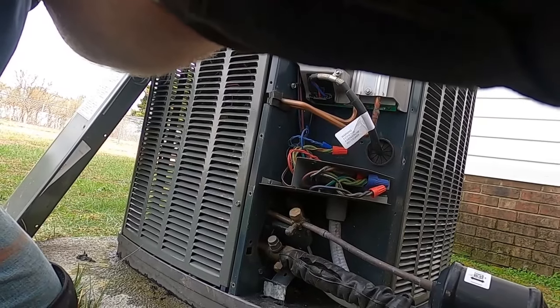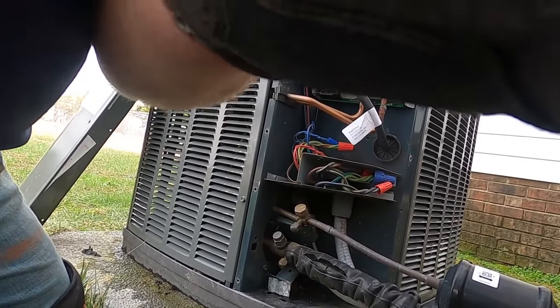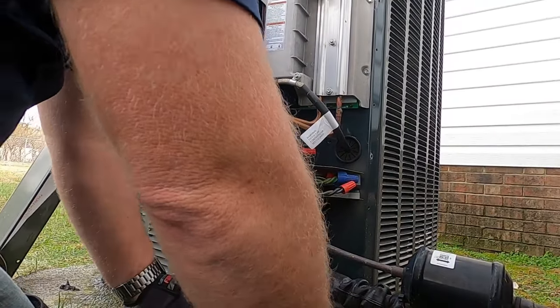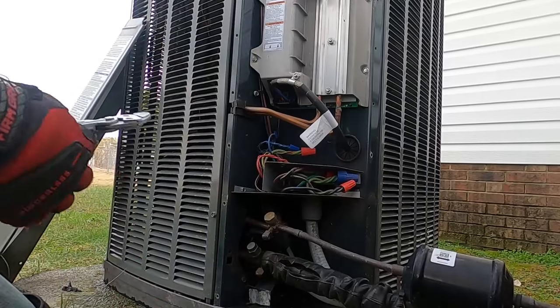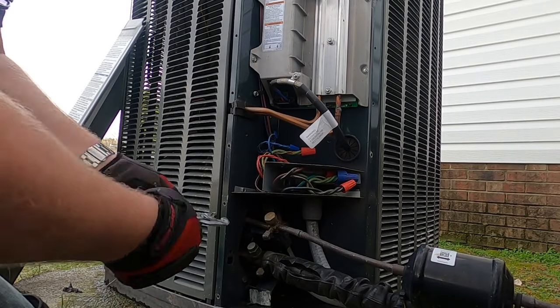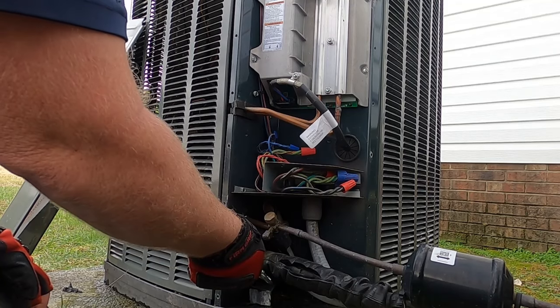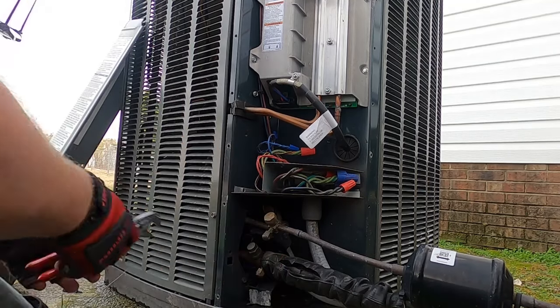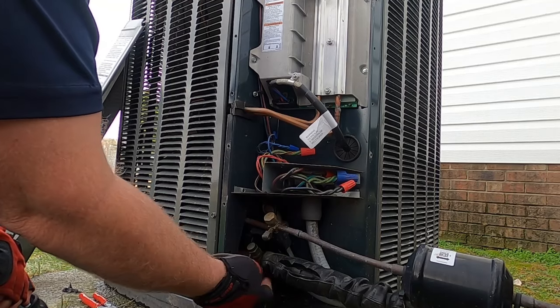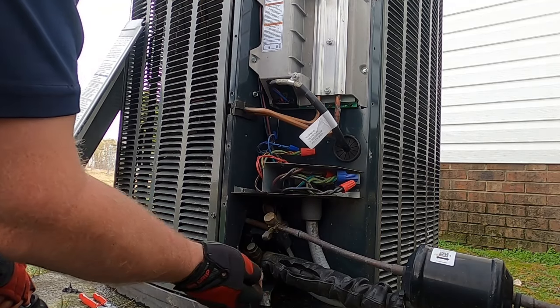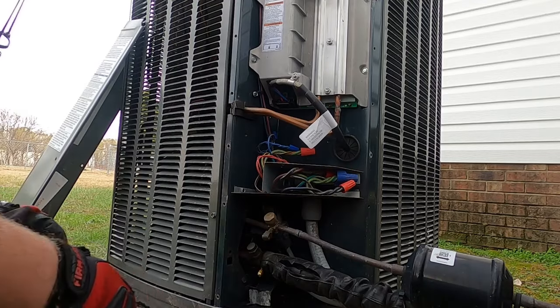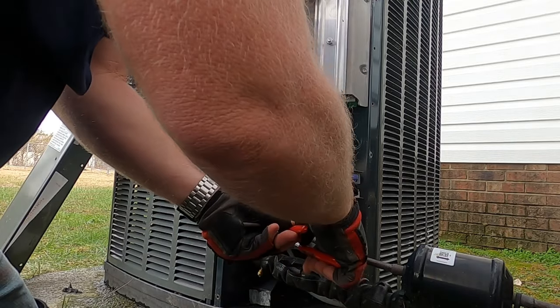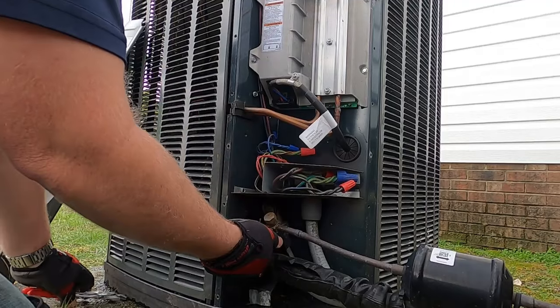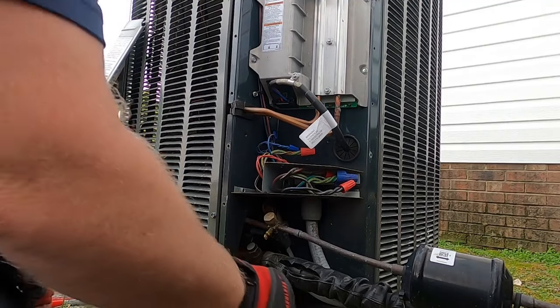Alright guys, I've got this thing on in cooling. 68 degrees outside, at 75 in the house, so I think I'll get a more accurate gauge on what my pressures are, superheat and subcooling, right now running it, and then I'll switch it into heat, test the defrost cycle, all that. But we get a lot of, I don't know, false calls. There's a little bit of pressure coming out of that thing when I opened it up. Might need to tighten that Schrader core a little bit, maybe replace it. But we're going to get hooked up to it, see what our superheat and subcooling are.